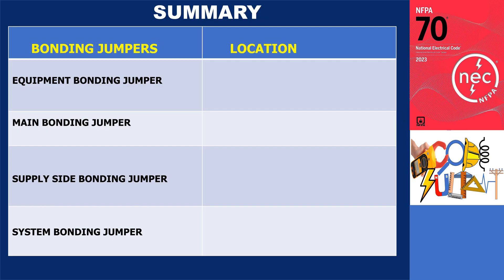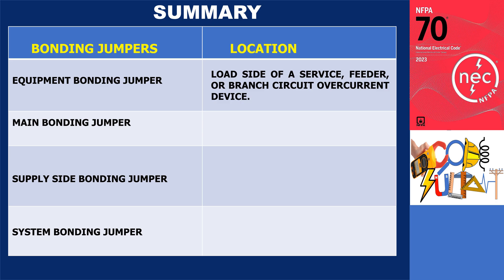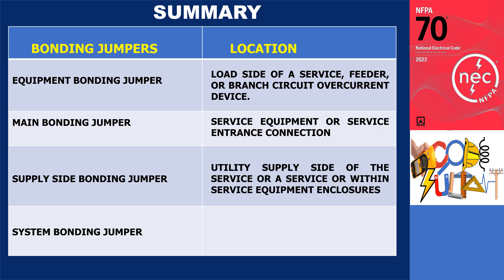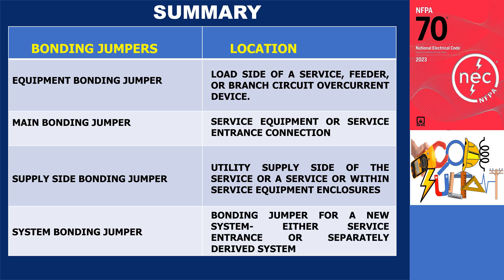In summary, the equipment bonding jumper is typically located at the load-side of a service, feeder, or branch circuit overcurrent device. The main bonding jumper is found at the service equipment or service entrance connection. The supply-side bonding jumper is positioned at the utility supply side of the service or within service equipment enclosures. Lastly, the system bonding jumper is installed as a bonding jumper for a new system, either at the service entrance or in a separately derived system. Understanding the various types of bonding and their significance is crucial for electrical safety and compliance with the code. Thank you for joining us on the Codesultant channel. Stay tuned for more valuable information on Electrical Code Rules and Best Practices.